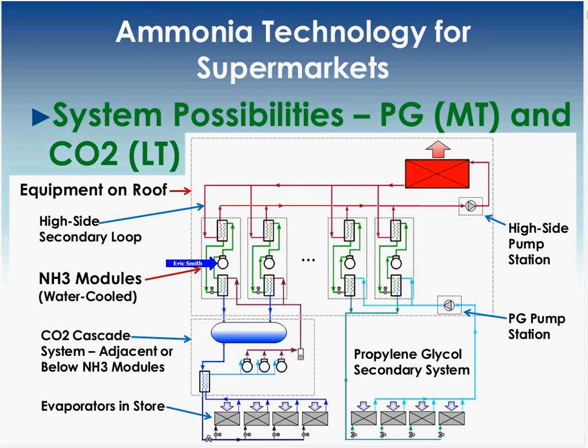I believe that a Japanese manufacturer has developed this, and to reiterate what Caleb was saying, use of copper in a system is not allowed, but what manufacturers are doing now is looking at using aluminum windings, and also using a miscible oil along the system. I bring this up because typically ammonia systems reject oil, and that is because the oil used is not miscible with the ammonia, and it has to be drained off. There are some new oils that are developed.